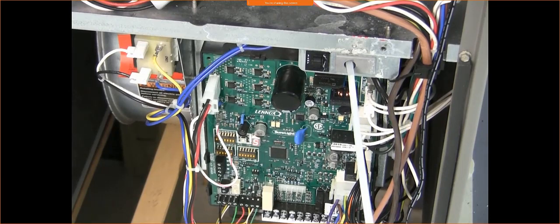So right here, this is an example of some of the newer technology that's coming out with furnaces. We've got a digital display. This one in particular has a single digit. Some of the other equipment out there is going to have a double digit. You know, it may tell you E5 or E250 or whatever the case may be. The display is a little bit larger. So that's really nice because we can recall the codes. So for example, up here where you put this wire tie, every system has a built-in safety. That safety is the blower door safety switch. What that does is it's there so that if the homeowner were to open up the door, we're not just going to suck in air through that blower door with it being off because we're bypassing the filter.